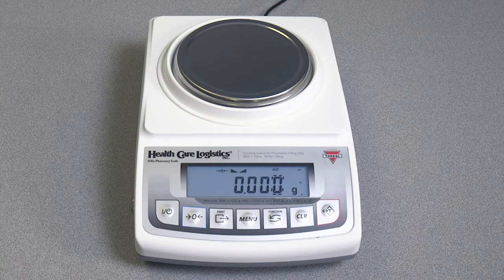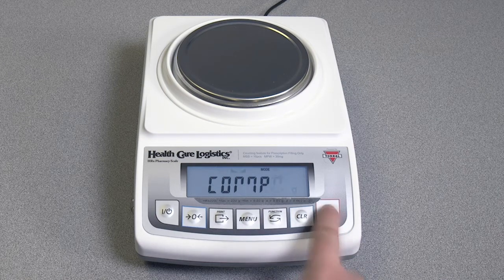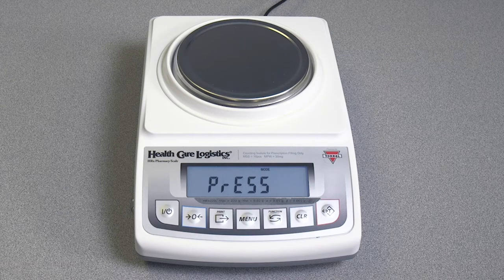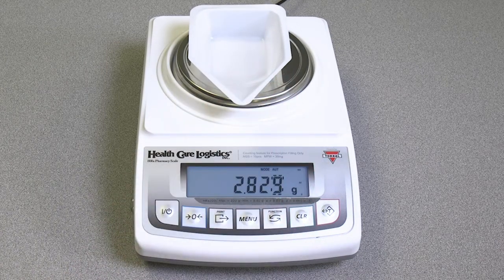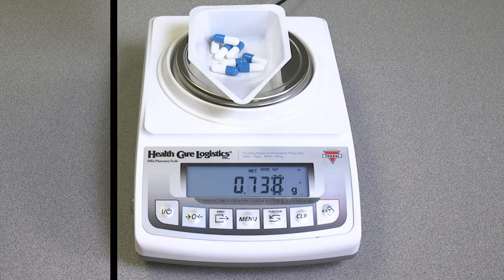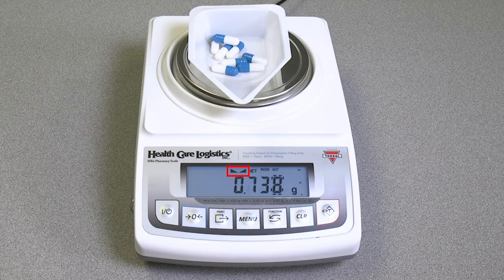To enter compounding mode, press the function key. When the word COMP appears, enable it by pressing the T key. Press tare will appear on the display. Place the weigh container on the plate and then press the T key. After the container is tared, ING01 will appear on the display, indicating that the scale is ready for the first ingredient. Add the ingredient until the desired weight is displayed and the stability indicator appears on the display. Once the desired weight is displayed, press the T key to store the ingredient's weight in the scale's memory.